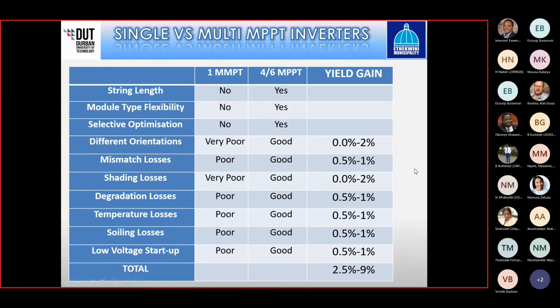So there are advantages of using an inverter with multiple maximum power point trackers versus a single one. And I think the table shows that there are a number of advantages with using multiple maximum power point trackers in an inverter. Ultimately, it could increase your production by between 2.5 to 9% for various different conditions. So you could use inverters with multiple MPPTs for panels installed in different orientations, in cases where you have some shading, where you have temperature losses, or if the panels are not clean. It also lowers your startup voltage, so it increases production ultimately.